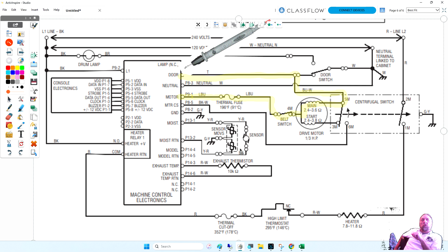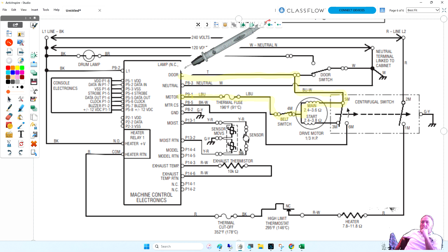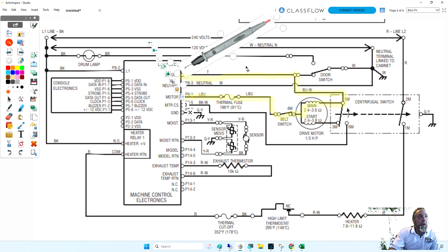Well, we have 0 volts there. What do we do? Backtrack. Backtrack where? More specific. Stop before you answer the question, because part of the circuit you don't see, and there is part of the circuit you do see. If I've got the meter lead on there, is that motor really getting power from that terminal? Where I have my meter lead, is that motor actually getting power from that pin on the board?